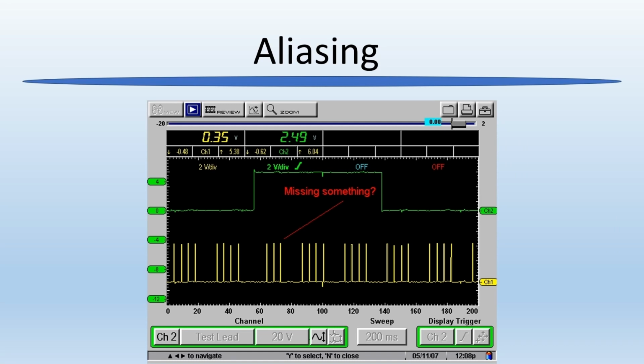So with the capture on the Snap-on, it is very possible that there were multiple sample points taken at the top of each square and every single pulse, including the missing pulse. So why then did it not draw it? Well, because the formulas they use are trying to account for anomalies and noise that is inherent to all electrical circuits, and maybe just some EMI from the surrounding area. So the scope may have seen the pulse, but decided it wasn't worth drawing it for whatever reason in their calculations. Maybe the sample interval was just too short, it thought maybe it was interference, or however they're averaging it, they decided not to draw it.